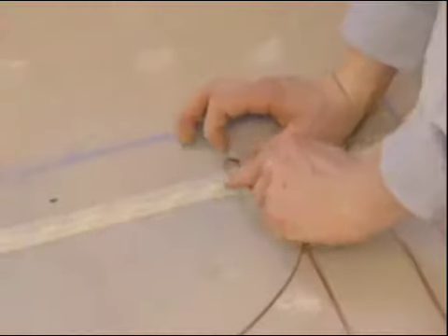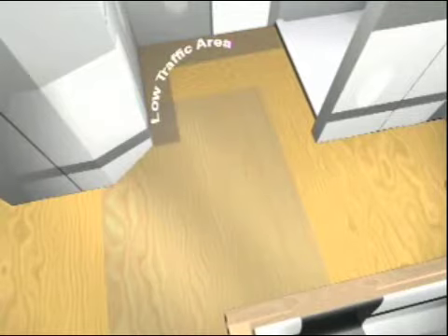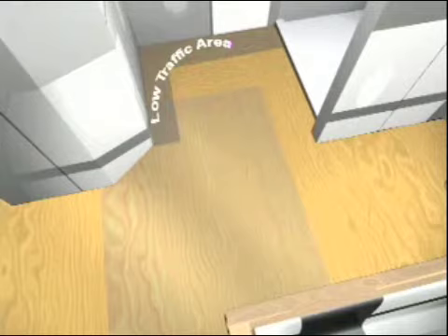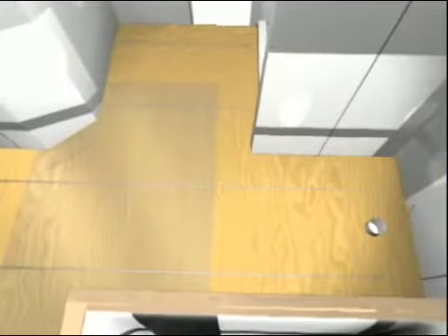For a room above an unheated area on concrete slabs or a high heat loss room such as a solarium, alternate the spacing from 3 inches apart, then 1.5 inches apart, then 3 inches apart, and so on. Carefully consider and mark low traffic areas on the rough sketch of the room's floor layout. Low traffic areas are typically along wall edges that can be left without cable up to 8 inches from the wall. Draw a strapping room layout on the room's floor layout.